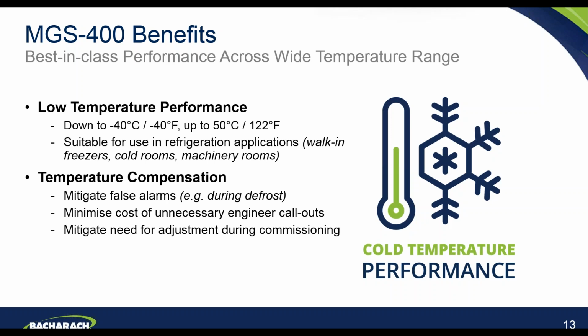What that is designed for really is to mitigate false alarms, particularly during defrost cycles, for example. Minimizes the cost associated with unnecessary engineer callouts. So if you had a false alarm and you called an engineer out, obviously there is a cost associated to that. And it also mitigates the need for some of the adjustments that might be necessary during the commissioning process.